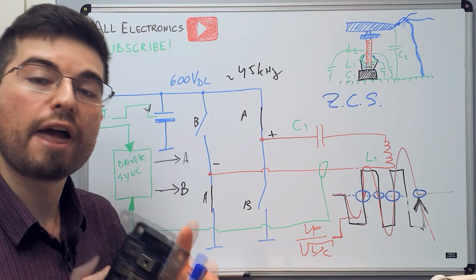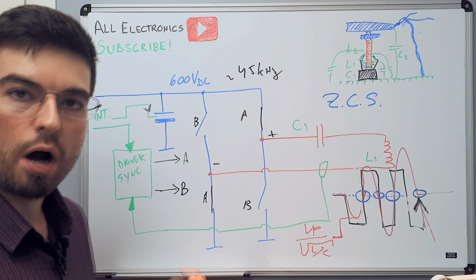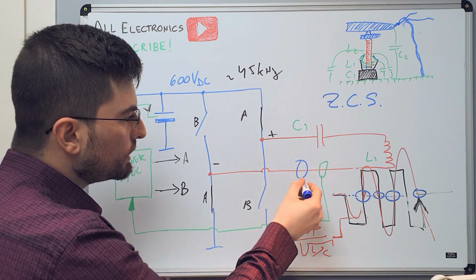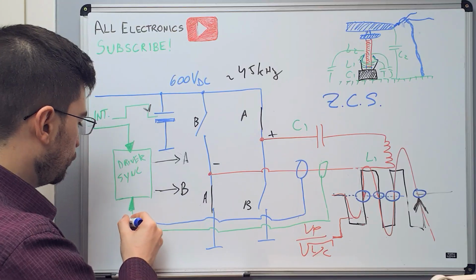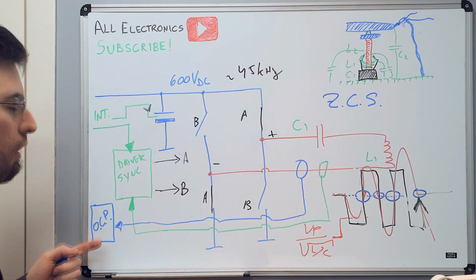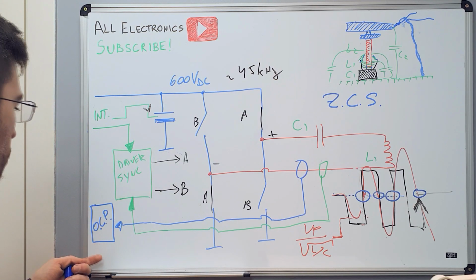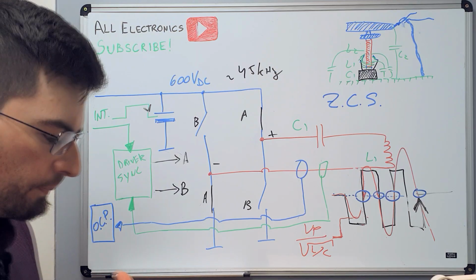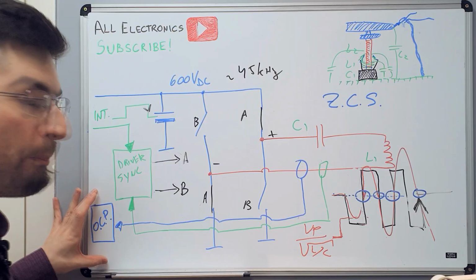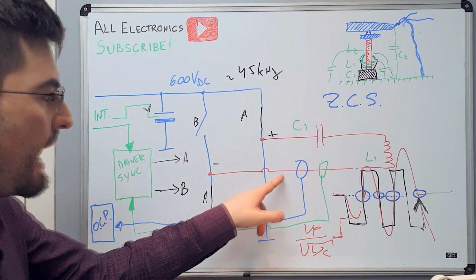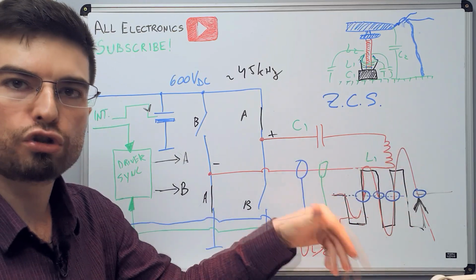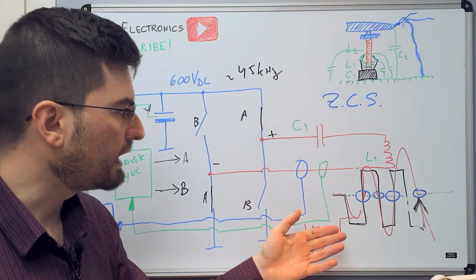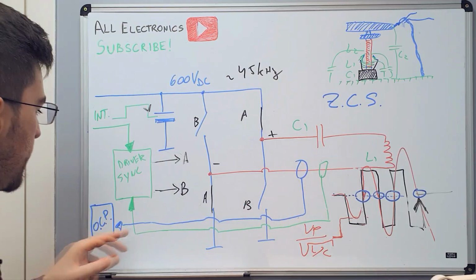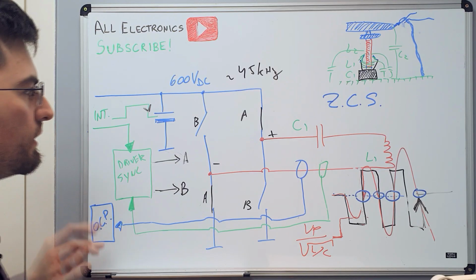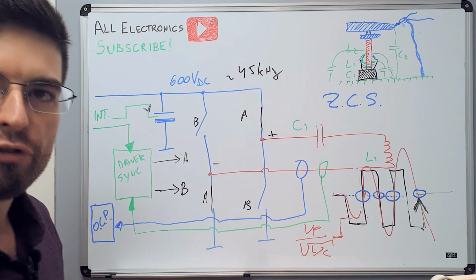This is very important. Here we commonly also have another current transformer that goes to a parallel circuit, overcurrent protection, or OCD, overcurrent detection. This is a safety measure. We have a parallel circuit detecting the current, and if it goes over a predefined limit like 2000 amps, if this condition is detected, we turn off the system to prevent further damage.